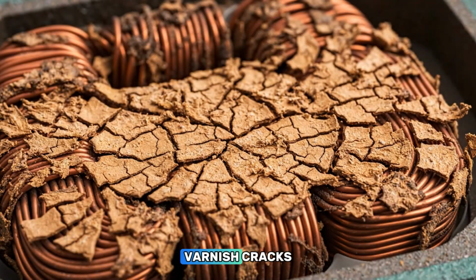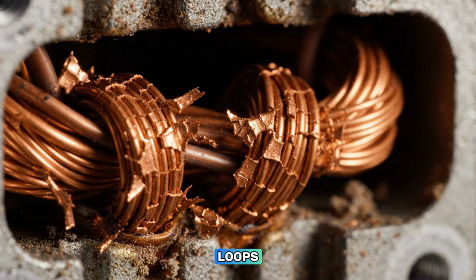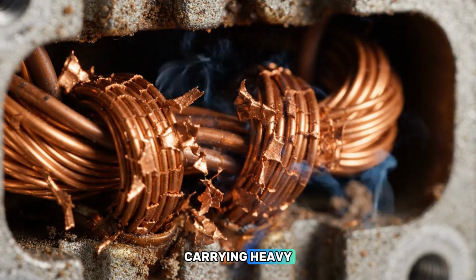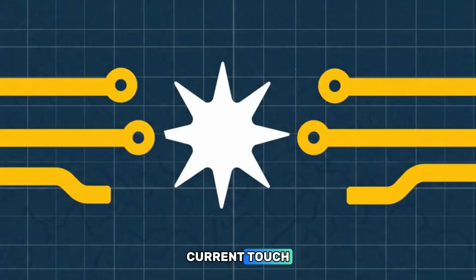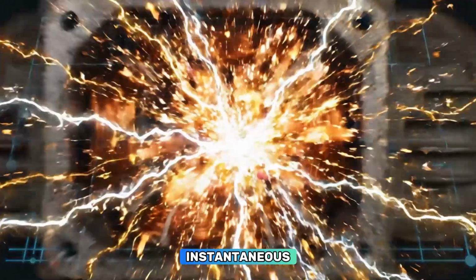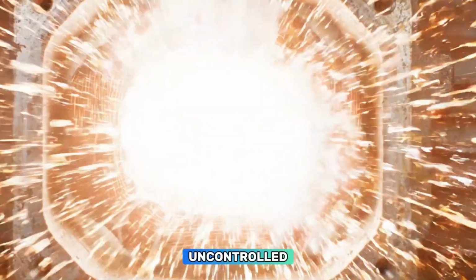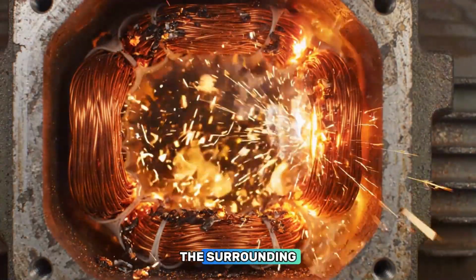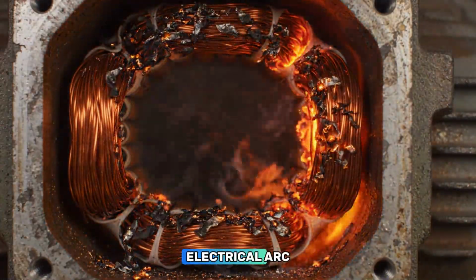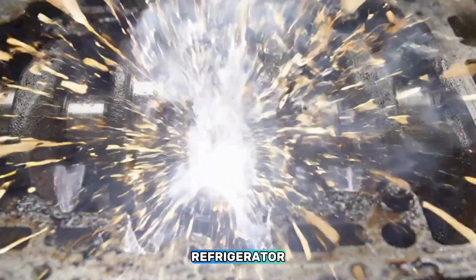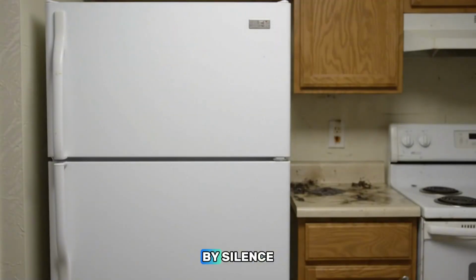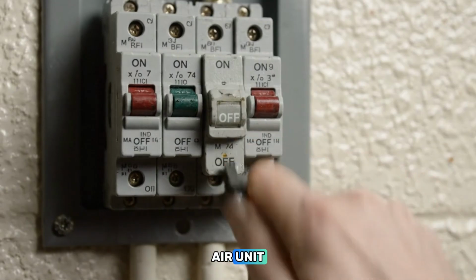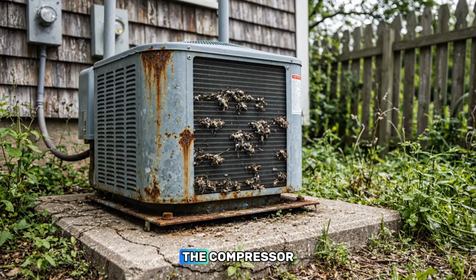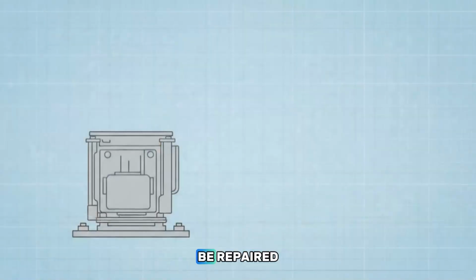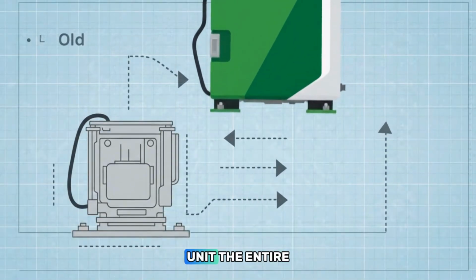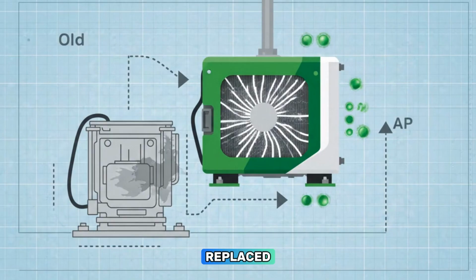Eventually, the brittle varnish cracks. Two adjacent loops of copper wire, carrying heavy, unmitigated current, touch. The short circuit is instantaneous and violent. The surge of uncontrolled electricity vaporizes the surrounding copper, creating a catastrophic electrical arc. In a refrigerator, you hear a loud click, followed by silence. In a central air unit, the main breaker trips hard. The compressor is dead. It cannot be repaired. It is a sealed unit. The entire system must be replaced.